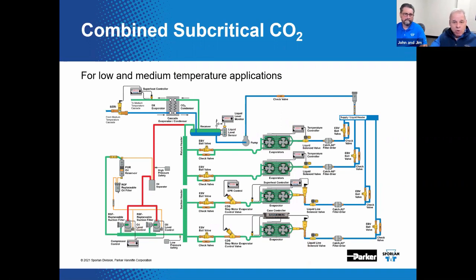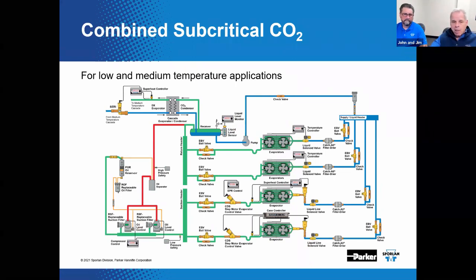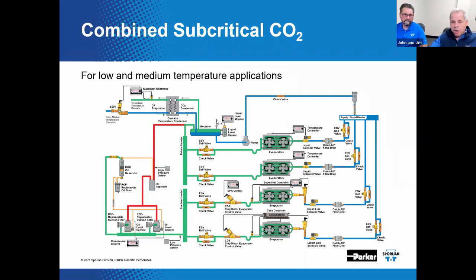The cascade portion is connected to compressor banks that lift the pressure to the medium temperature requirement. Note the same operation occurs. This application just optimizes the use of the heat exchangers, receiver, tank, and pump as far as how many you need in the system to get the job done.